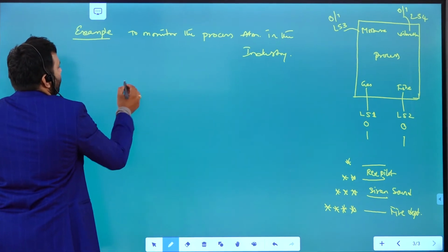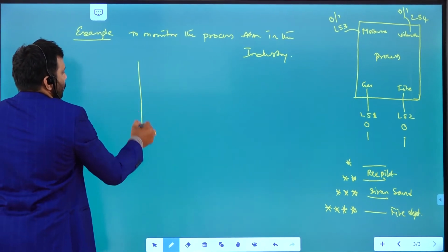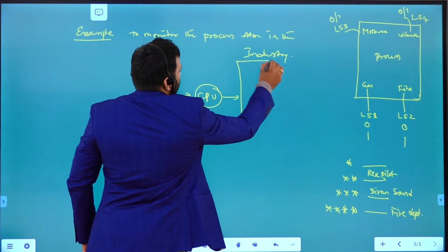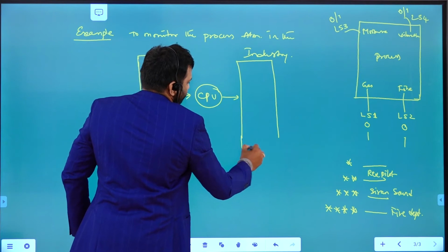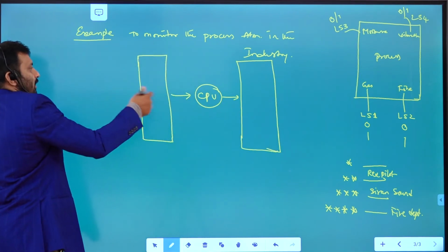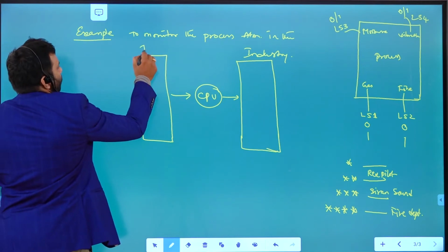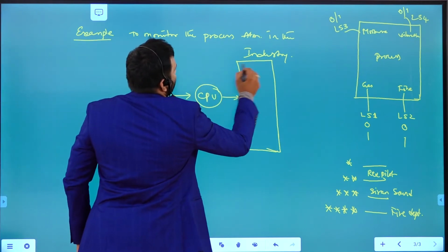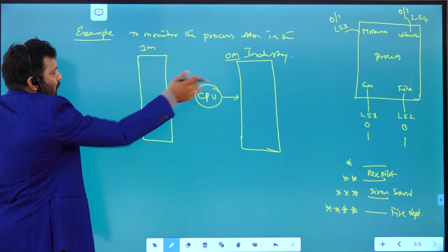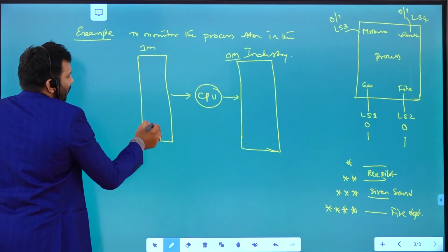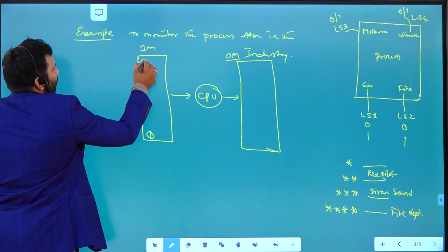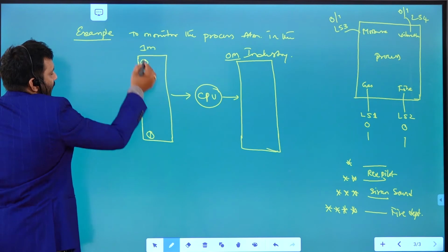How are we going to connect now, right? This is the way you need to connect. The sensors are connected to the input module, and the actuators are connected to the output module, right? So previously also we have seen the input module, right? This one is the output module, right? So how many inputs are there? 4 inputs are there, right? You know, the ground terminal is there, as well as the power supply terminal. In between, 8 terminals are there.